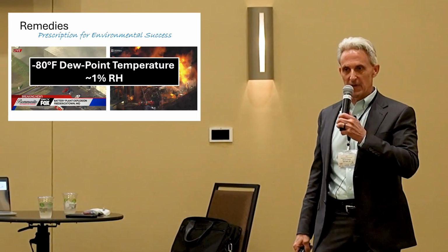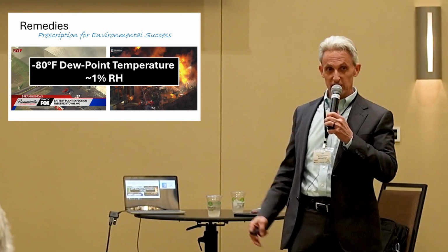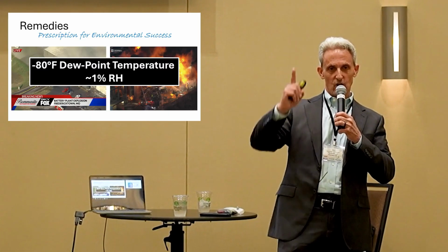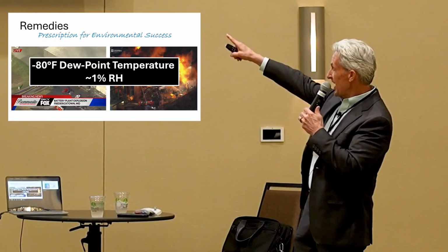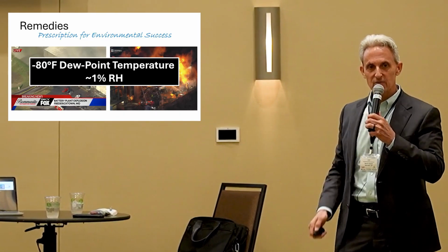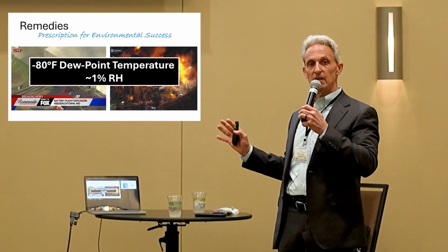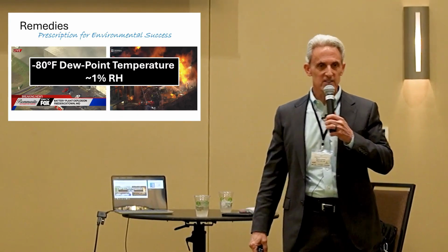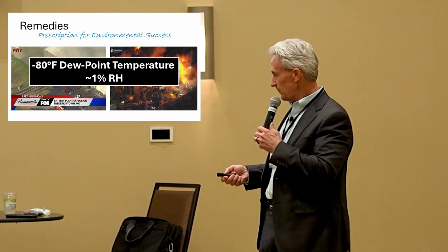That's the equivalent of the amount of moisture in negative 80-degree Fahrenheit air if you could cool it traditionally, which you cannot because moisture would have been frozen on that coil way up the temperature scale range, right? But at a negative 80-degree supply air dew point, I can maintain a lithium battery manufacturing plant at about 1% relative humidity. Amazing. And if I can do this here, man, I can do it easy in hospitals. That's light lifting for solid desiccant dehumidification, okay?